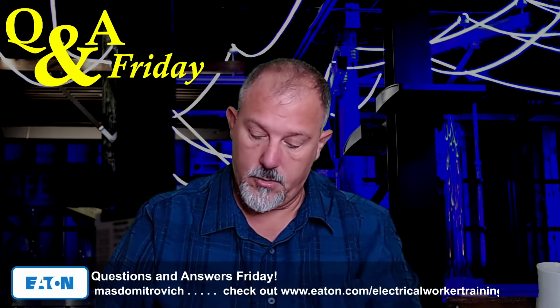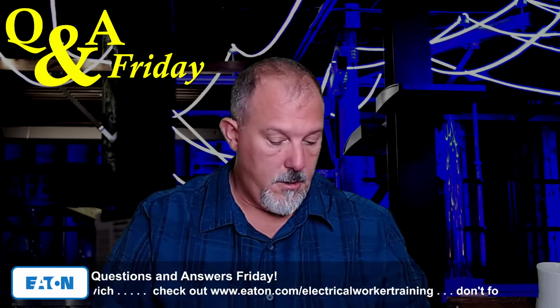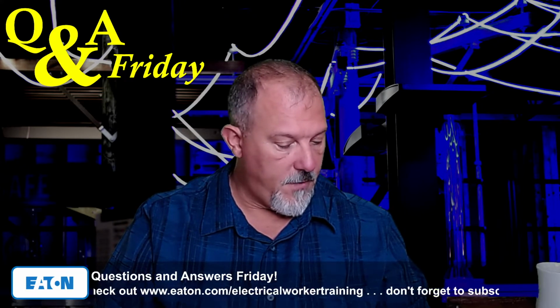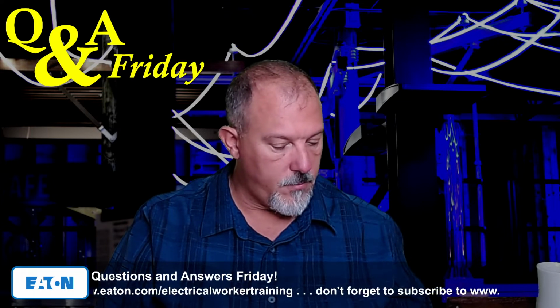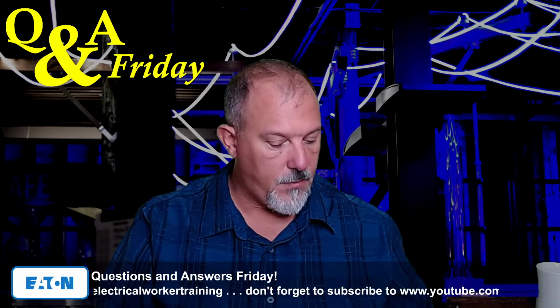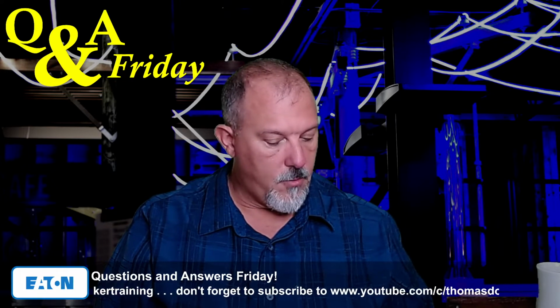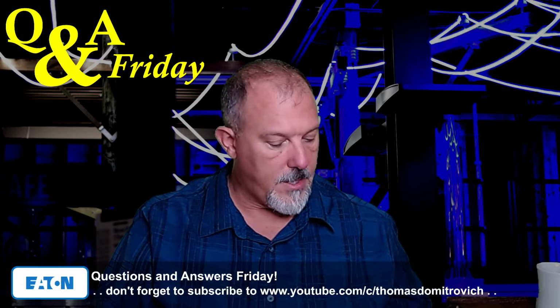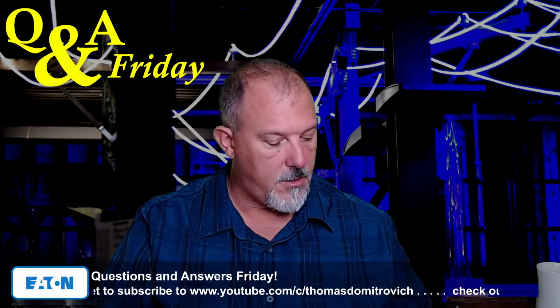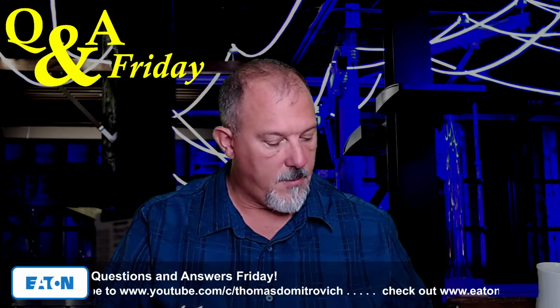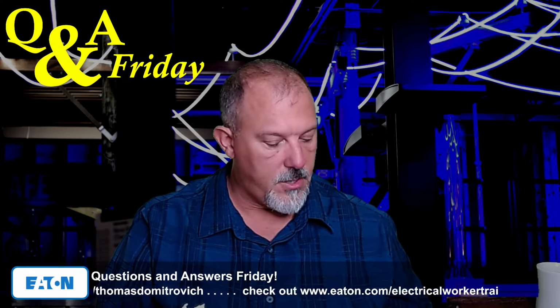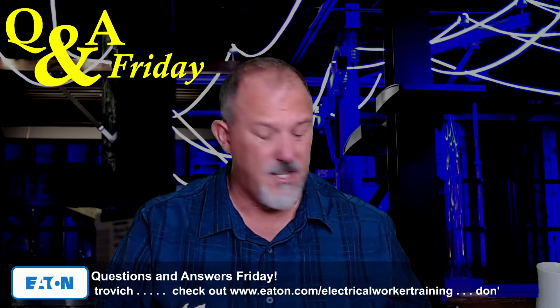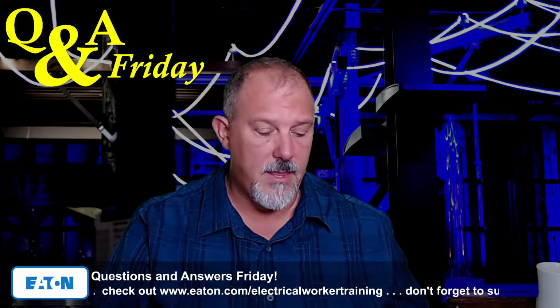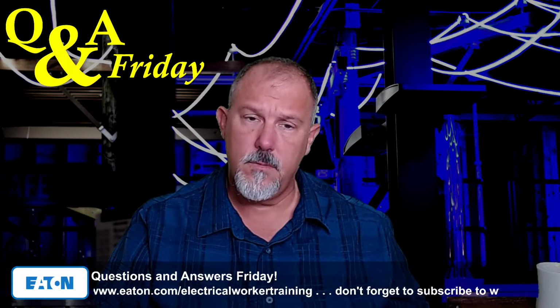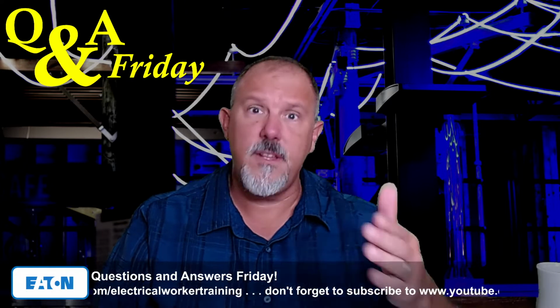L, so 230.95, let's take a look at 230.95. Ground-fault protection of equipment shall be provided for solidly grounded wye electrical services of more than 150 volts to ground but not exceeding 1000 volts phase to phase for each service disconnecting means. The rating of the service disconnect shall be considered to be the rating of the largest fuse that can be installed or the highest continuous current trip setting for which the actual overcurrent device installed in a circuit breaker is rated or can be adjusted. So you don't do that. I don't think you can go there. It's still an overcurrent device, even if you're not using it.